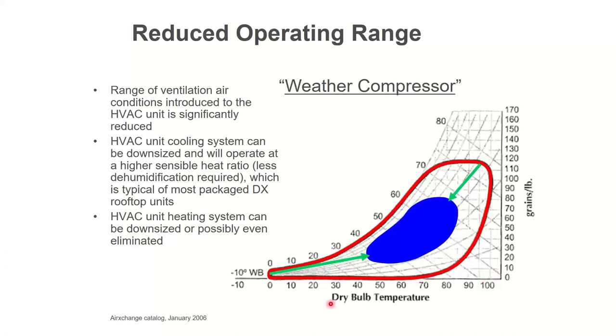But if my outside air humidity is the problem, think of it like this. This is my psych chart. My normal air handler or rooftop has to handle this really cold day over here, my really hot day, my really humid day, my really dry day. It's got to cover everything and it doesn't do it very well. If the ERV preheats the air from the red to the blue, pre-cools it from red to blue, pre-dehumidifies it from red to blue, pre-humidifies it from red to blue, now my air handler only has to deal with the blue blob instead of the red blob.